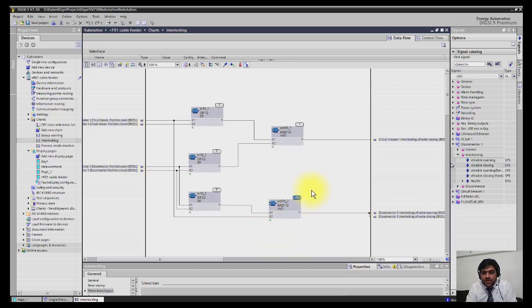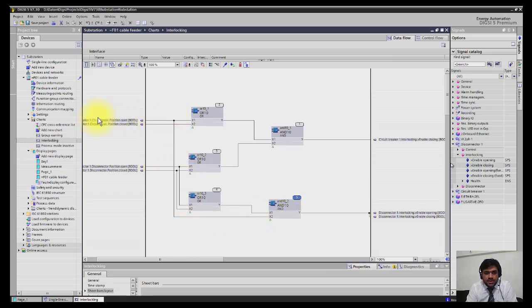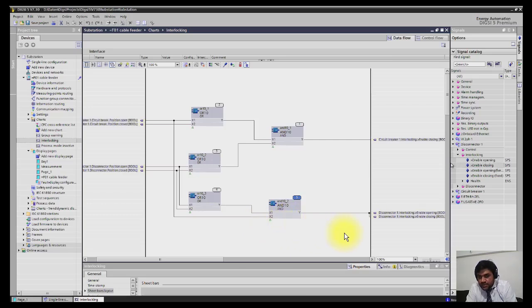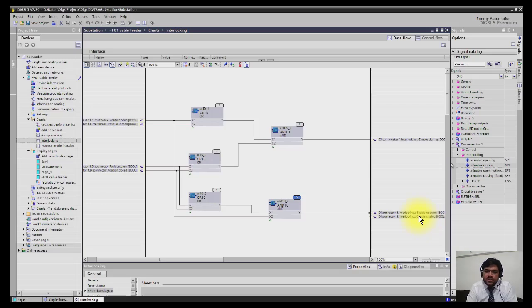In the same way you have to make interlocks for the isolator. So isolator can only be operated, this is first input here, if the breaker is in open position, just link it to x2. Or the isolator should have very clear status, either it should be open. If it is intermediate you should not be able to operate the isolator. I have just connected it to enabling open level, enabling close. This is the way how it works here.